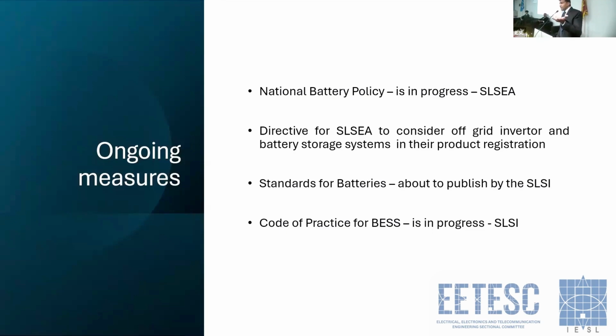So with the agreement they have with the customs, non-standard products are not coming to Sri Lanka. At the moment, only grid-connected inverters are filtered through this process. So we gave a directive, and they agreed to consider storages as well as off-grid inverters. And for the standard for batteries, we have worked with the SLSI. They have already prepared it and are going to publish the SLSI, that means an adopted standard. In addition to that, they are going to prepare a code of practice for battery storage as well. All are in progress at the moment.